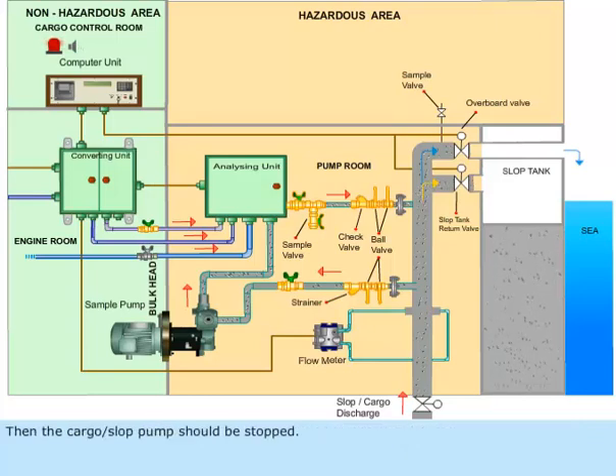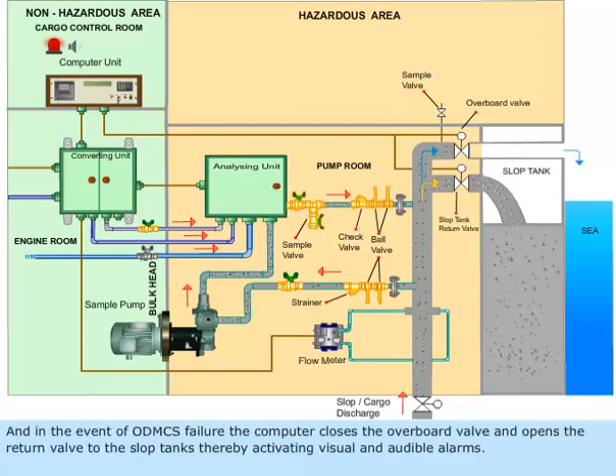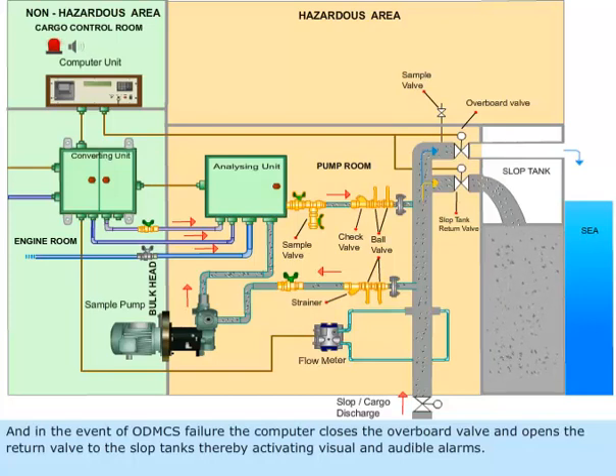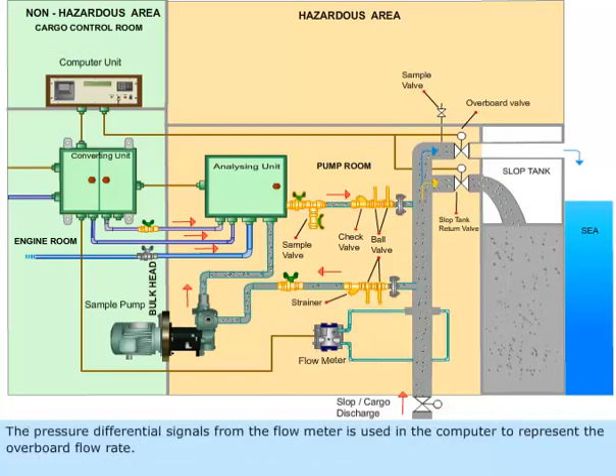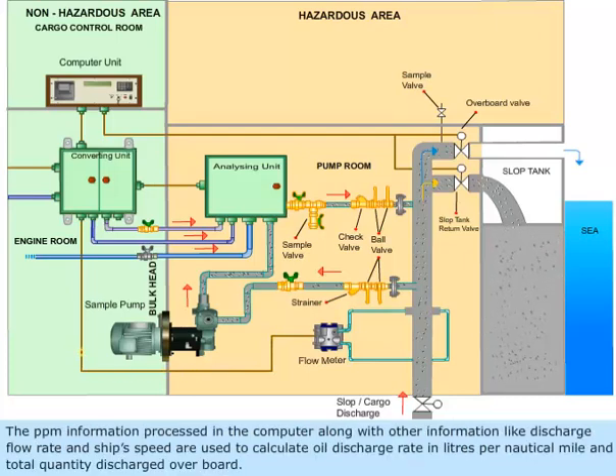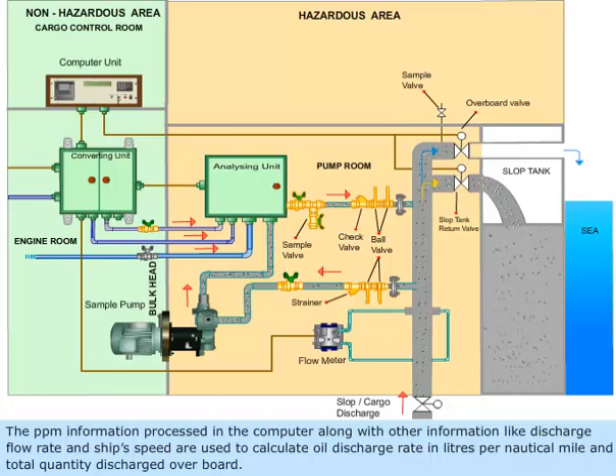The cargo or slop pump should then be stopped. In the event of ODMCS failure, the computer closes the overboard valve and opens the return valve to the slop tanks, thereby activating visual and audible alarms. The pressure differential signals from the flow meter are used in the computer to represent the overboard flow rate. The ppm information, along with discharge flow rate and ship speed, are used to calculate the oil discharge rate in liters per nautical mile and total quantity discharged overboard.